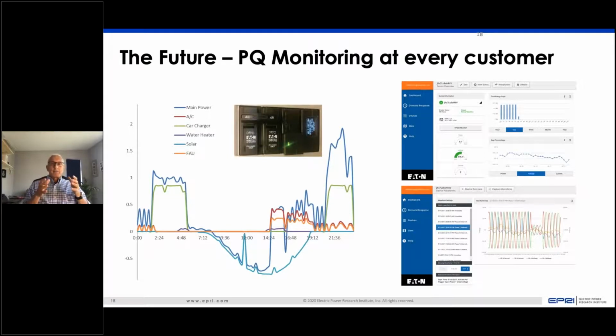There's so much information in the waveform when we're measuring power quality—it's more than just the RMS voltage and current characteristics. Actual waveforms are going to open up whole new areas of diagnostics as we get them from everywhere in the grid. The current waveforms in particular are so rich in diagnostic information about what happened that having monitors always recording voltage and current waveforms will be a critical part of future grid monitoring.